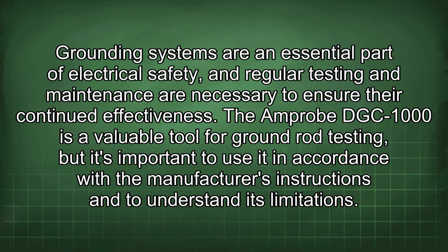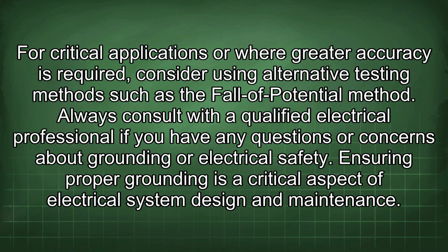Grounding systems are an essential part of electrical safety, and regular testing and maintenance are necessary to ensure their continued effectiveness. The Amprobe DGC-1000 is a valuable tool for ground rod testing, but it's important to use it in accordance with the manufacturer's instructions and to understand its limitations. For critical applications or where greater accuracy is required, consider using alternative testing methods such as the fall-of-potential method. Always consult with a qualified electrical professional if you have any questions or concerns about grounding or electrical safety.